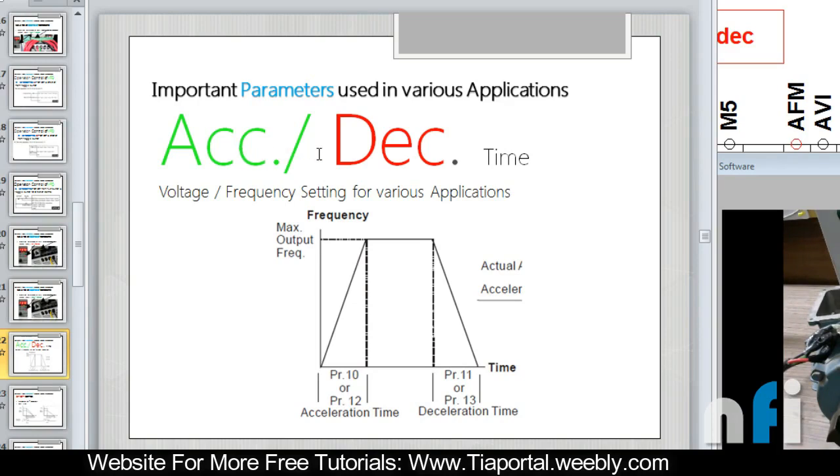For example, if a motor is running at 15 Hz, it is given a command of 50 Hz, so the time taken by motor to reach from 15 to 50 is the acceleration time. And when I press the stop, then the time taken by motor to reach from 50 back to zero is the deacceleration time.